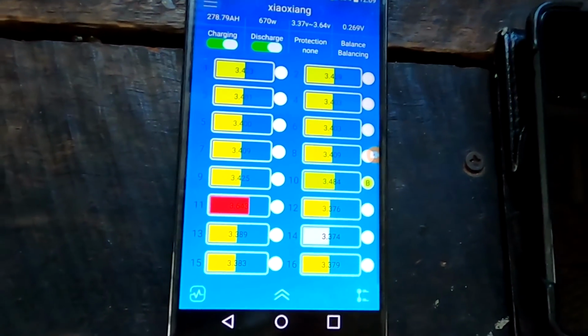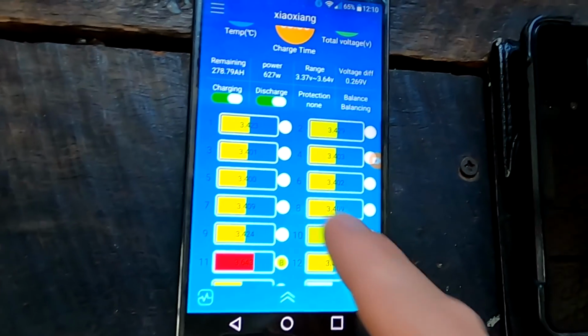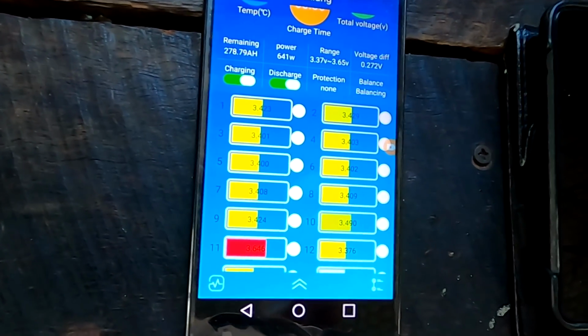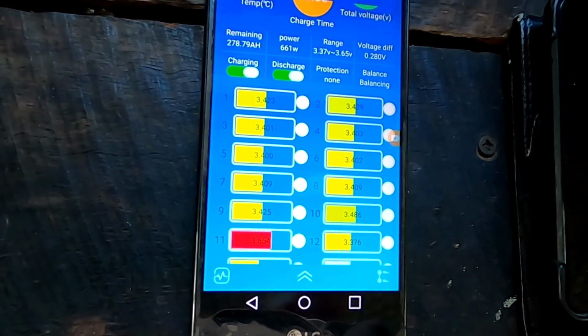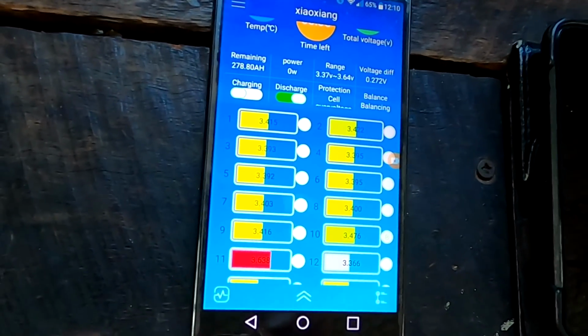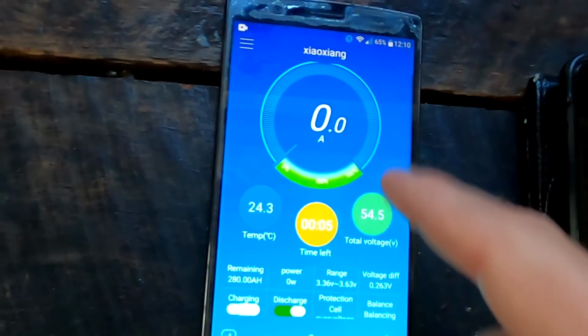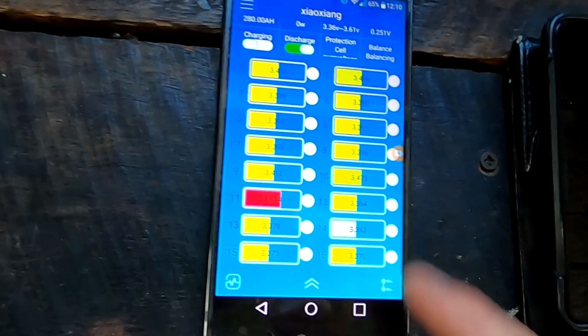So this goes off at 12.2 amps for these two cells, at 3.64 volts. We should see the charge button turn off at 3.65, with a bit of delay depending on the settings. We're over 3.6 now. Yeah, it has turned off the whole battery bank. Zero amps going in.